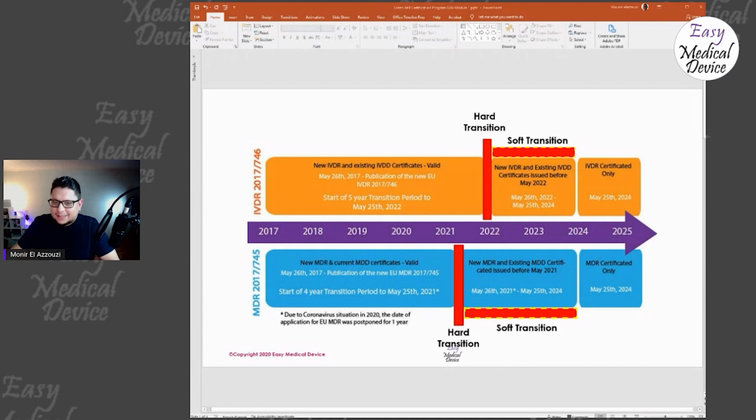If you're also a pharmaceutical company that uses a medical device, so combined products like combined medical device and drug, you have Article 117, and from this date, the same, your product should now follow the EU MDR. So you have to get a statement from the notified body about, for example, your syringe, if it's a pre-filled syringe, that your syringe is really following Annex 1 of the EU MDR, etc. So you see those products.